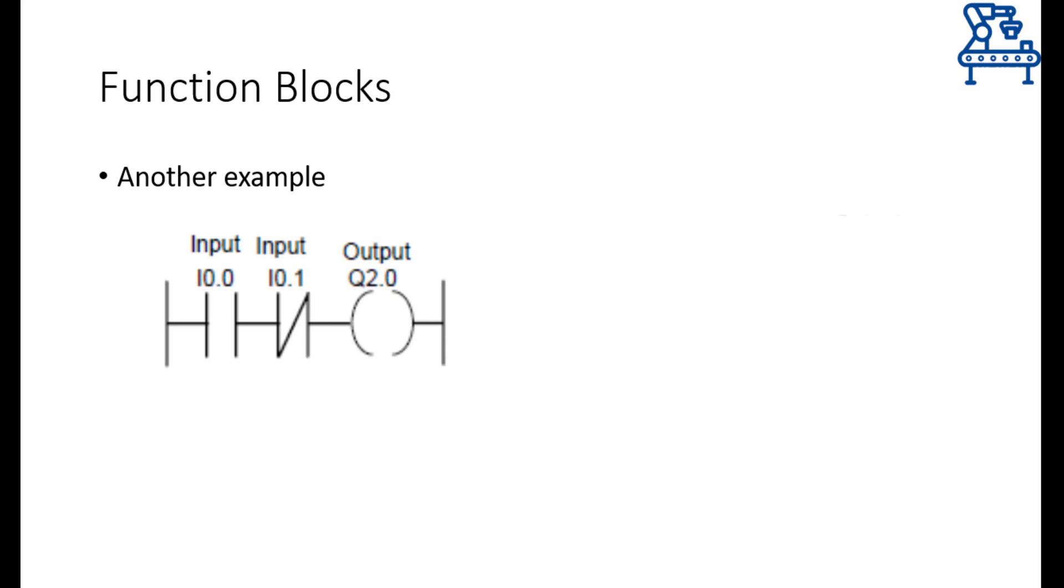Similarly, consider this diagram. Note that this ladder diagram is performing AND operation between two inputs but input I0.1 is normally closed contact. So, to implement this thing through function blocks, you just need to AND the two inputs but the input I0.1 should be inverted first. Therefore, this function block diagram represents the logic implemented by the ladder diagram shown over here.